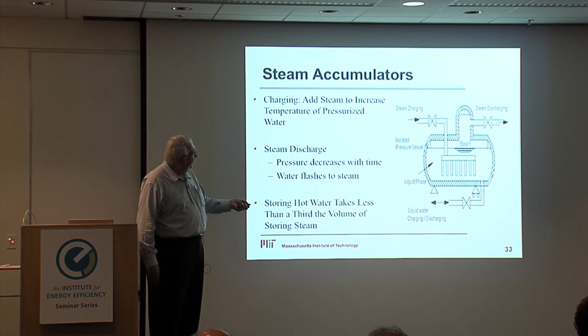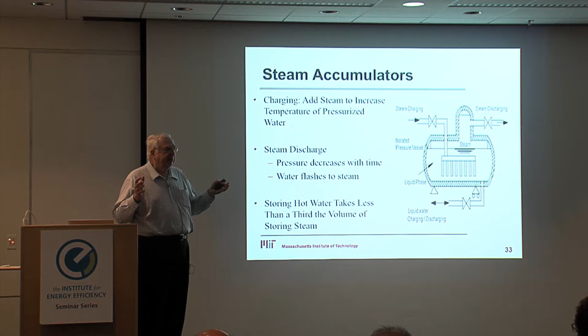One is the steam accumulator, and the second is sensible heat storage. What's a steam accumulator? We have a big tank of cold water. When we have excess energy in our power production system, excess steam, we use the steam to heat the water up to its saturation point, its boiling point. On discharge, when we want extra power, we open the valve, flash steam, and the steam goes to the turbine or the feed water heaters within the steam cycle. We store the heat as hot water because it takes less than 1/3 of the volume of storing hot, compressed steam. Strictly economics.